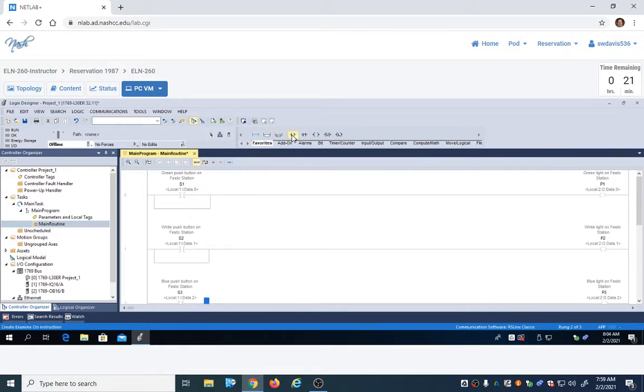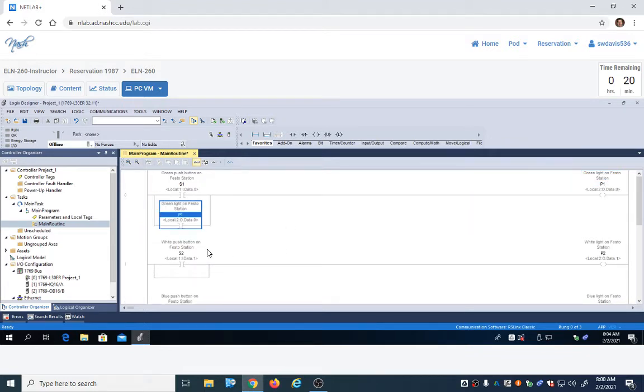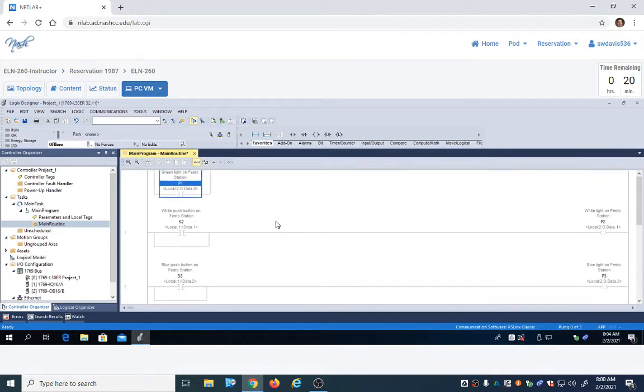So the way we do that is the same way you would do it in a motor start circuit, okay? You would use part of whatever you're controlling in the output. We use an instruction here that says, if this output comes on, or this address here comes on, or it closes, let's keep it on, all right? So now when we hit S1, when we press the button, this output will energize. Once this output energizes, it's going to keep that address on, and now we'll have a path to our output this way. All right. So you're going to do that for each one.